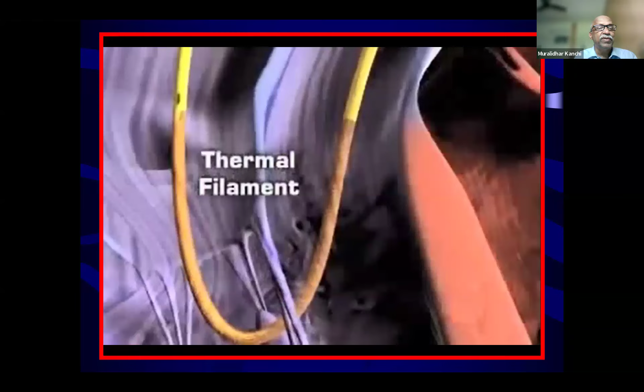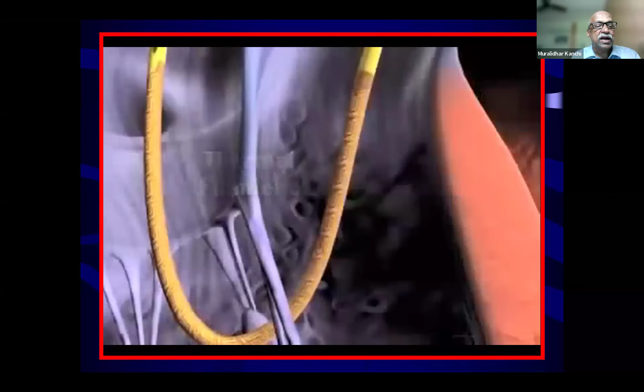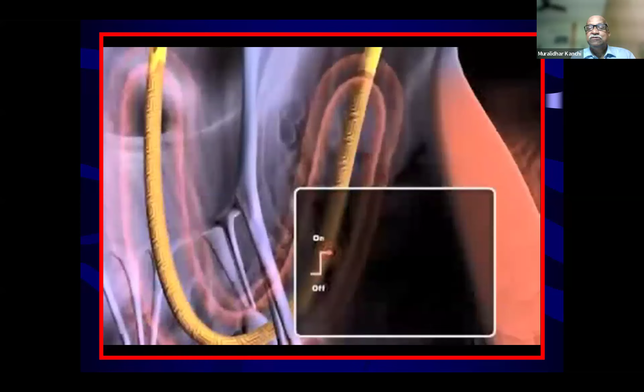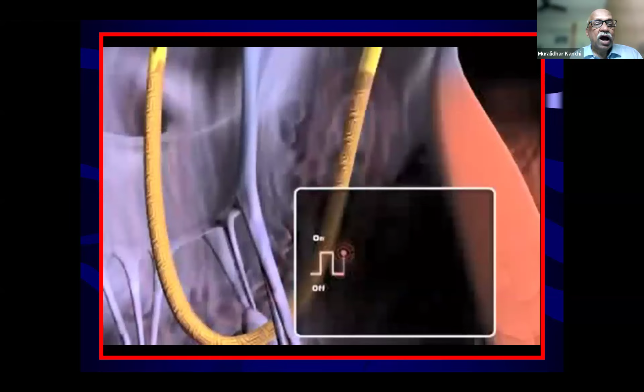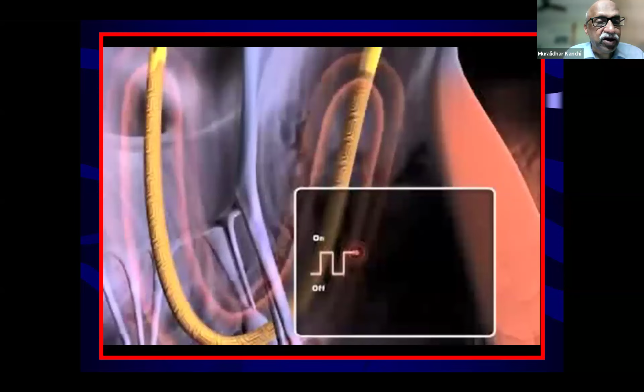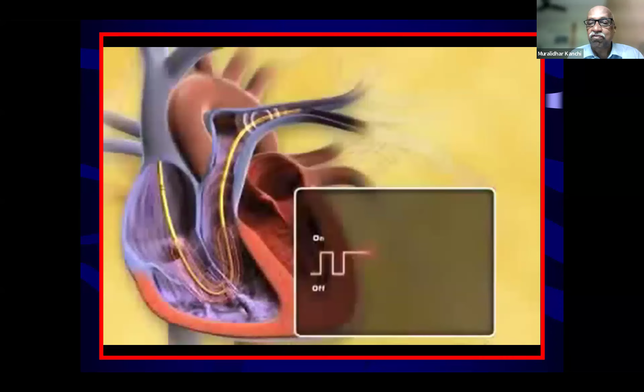Similarly, in the continuous cardiac output catheter, there is a thermal filament incorporated in the structure of the catheter itself, which is heated in a pseudo-random fashion to about 40 degrees centigrade, and the resulting increase in temperature is sensed at the tip of the catheter. And here you get the heating curve rather than the cooling curve. In the intermittent technique, where you use cold saline, we get the cooling curve, whereas here it will be a heating curve.